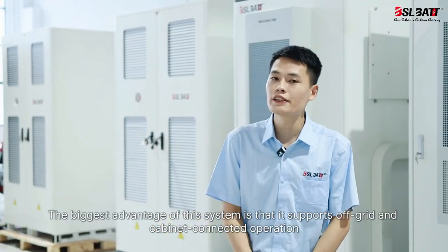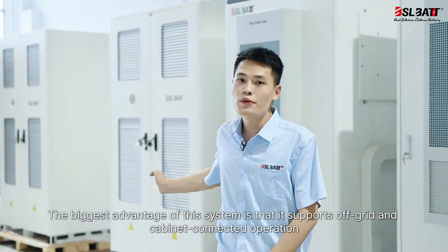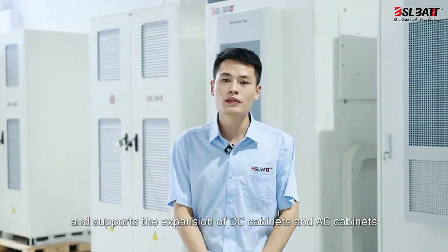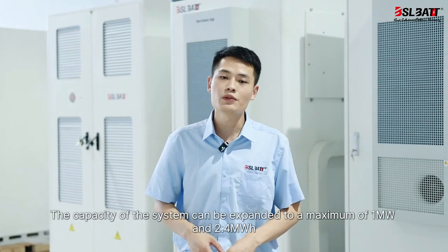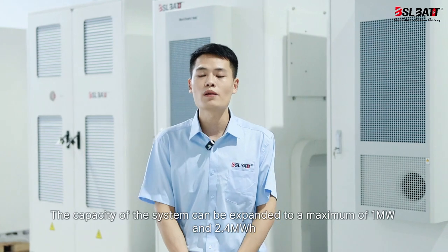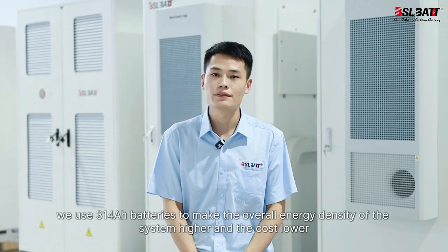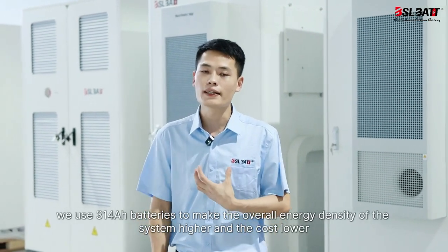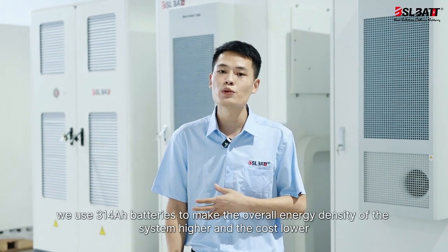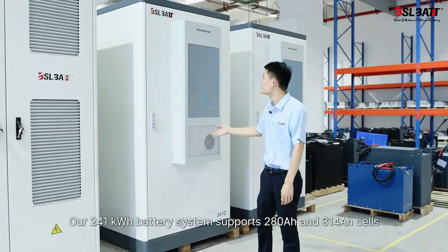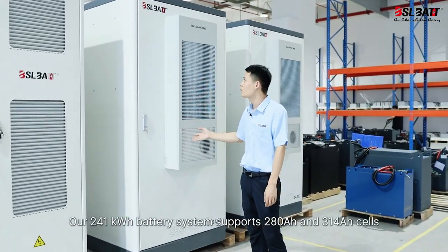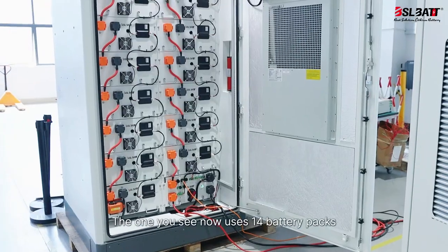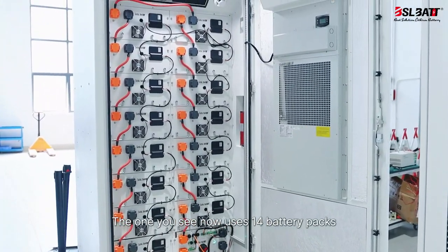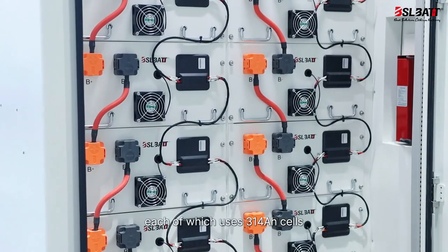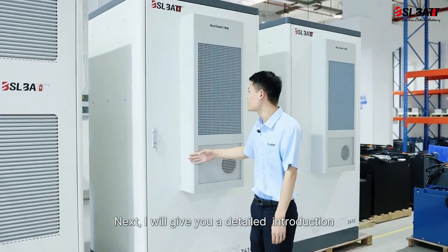The biggest advantage of this system is that it supports off-grid and cabinet-connected operation, and supports the expansion of DC cabinets and AC cabinets. The capacity of the system can be expanded to a maximum of 1 megawatt and 2.4 megawatt hours. In addition, we use 314Ah batteries to make the overall energy density of the system higher and the cost lower. Our 241 kilowatt hours battery system supports 280Ah and 314Ah cells. The one you see now uses 14 battery packs, each of which uses 314Ah cells. Next, I will give you a detailed introduction.